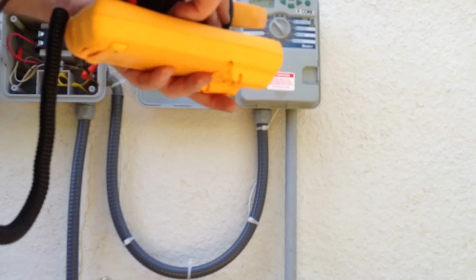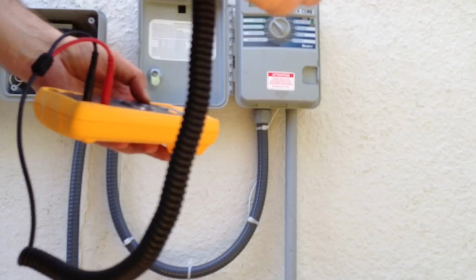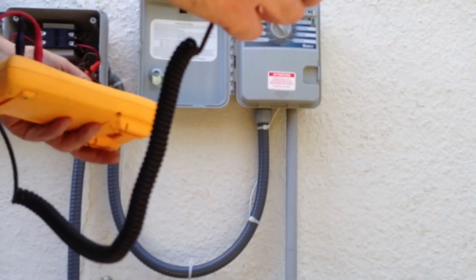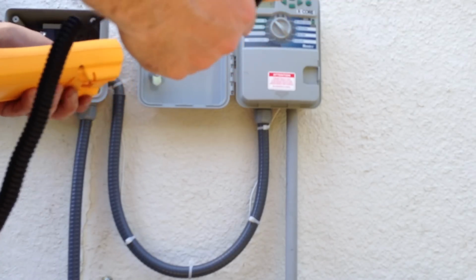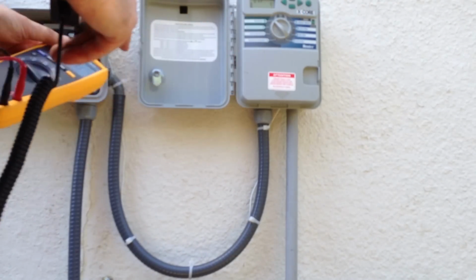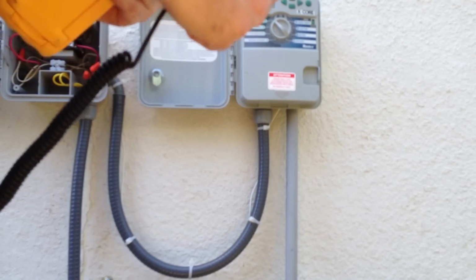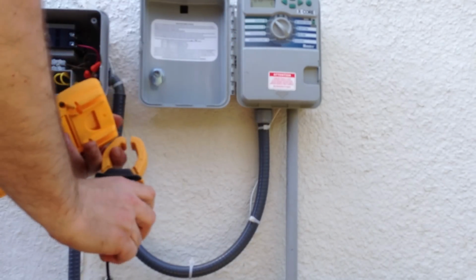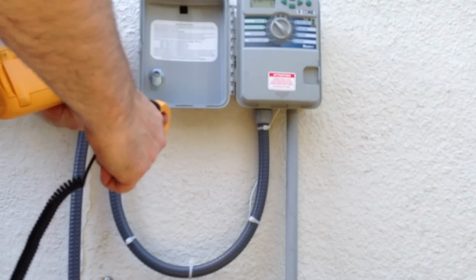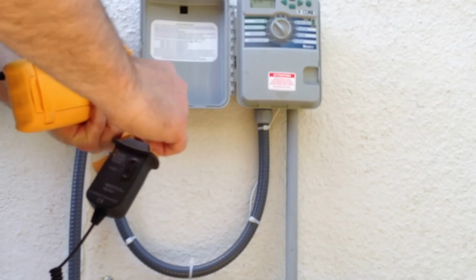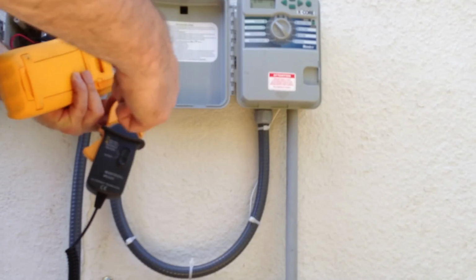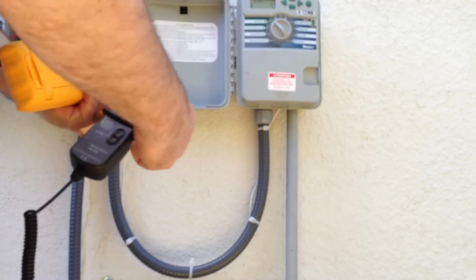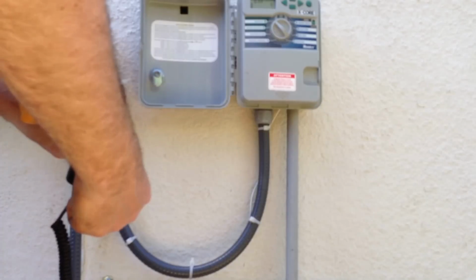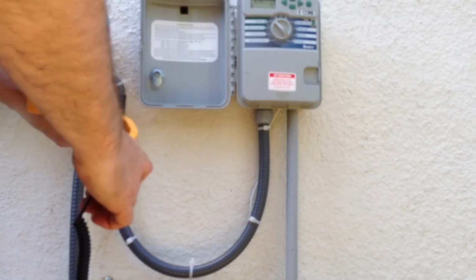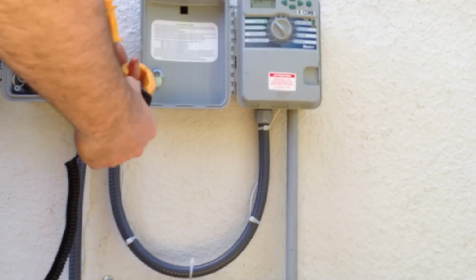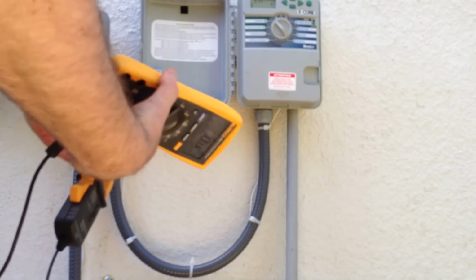So what this does is basically convert amps to millivolts. It measures the amps on a wire, and the benefit is you don't have to run the wire through the multimeter to measure the current flowing through. You can just use this. I think it works the way a transformer works on the light pole. It's basically like a magnet, and as the electricity runs through, it pulls off some of the electrons and measures them. It's able to measure the amps, and then it converts that into millivolts, which this multimeter can measure.